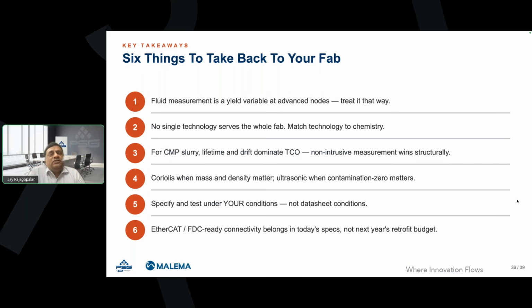So we should match the technology to the chemistry as well as the application. For CMP slurry, lifetime and drift dominate as we looked at it. So what sort of studies has the vendor done to validate the lifetime of the product? Because one failure in the tool means the maintenance engineer has to gown up and get into the tool. You have to shut down the tool, take it out, and it's quite an expensive exercise. So a very reliable product is extremely important.